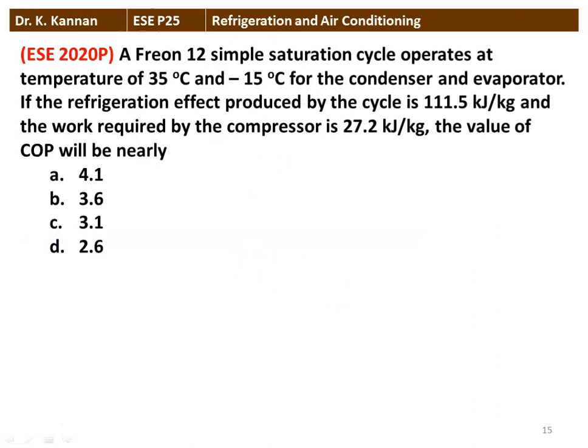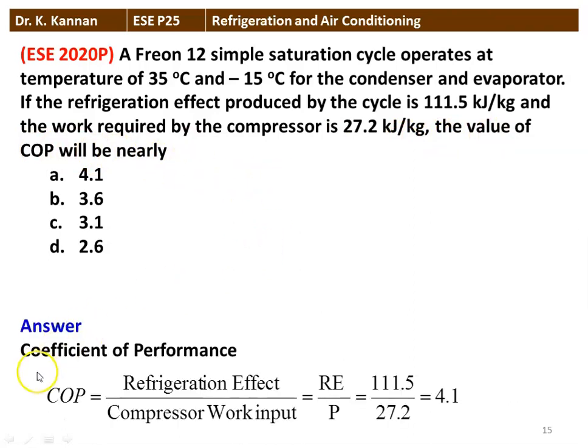The next question from the 2020 question paper: a simple saturation cycle operates at 35°C and -15°C for the condenser and evaporator. The refrigeration effect is 111.5 kJ/kg and the compressor work is 27.2 kJ/kg. The COP equals refrigeration effect divided by compressor work: 111.5 ÷ 27.2 = 4.1. The correct answer is COP 4.1. Note that while temperature data allows calculation of theoretical COP, actual COP uses refrigeration effect and compressor work input.